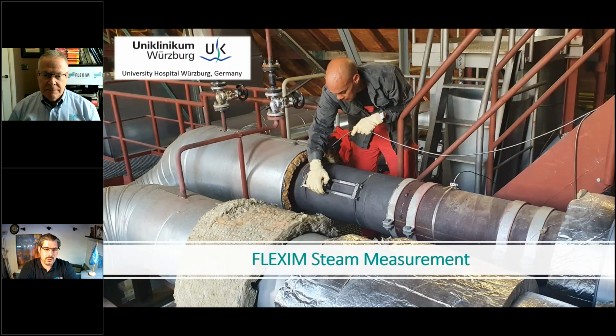Again, here, our transit time measurement, and the same applies to steam. So we just made this steam measurement. We installed a steam measurement yesterday in the University Hospital Würzburg in Germany. As you can see here, this is the full pipe diameter. There's no need whatsoever to reduce the pipe diameter to have this measurement. You can see our service colleague here is just mounting the transducers on this mounting rail. This is a portable installation, so this is not a fixed one. This is temporary, and is supposed to sit there for 2 weeks to have a boiler survey.